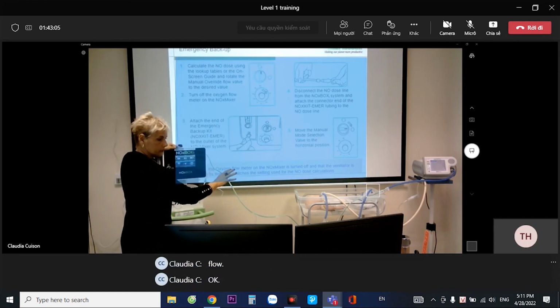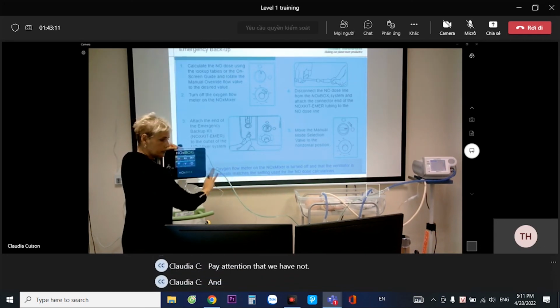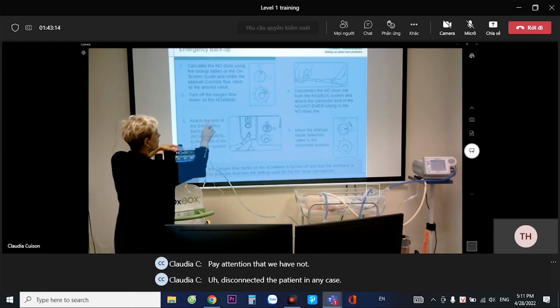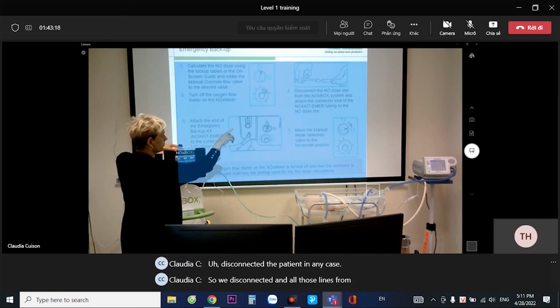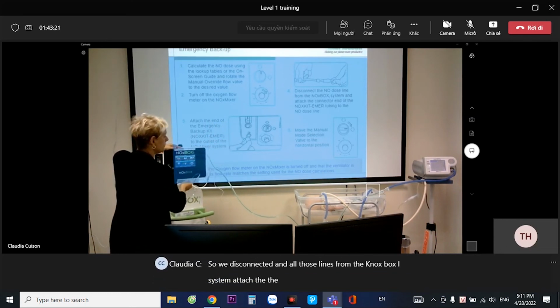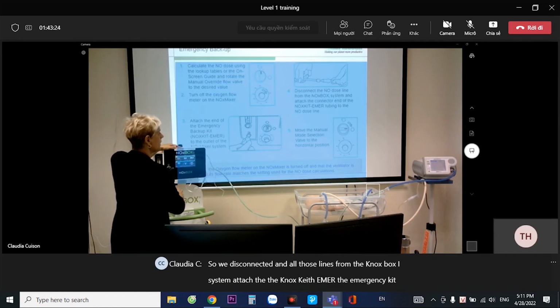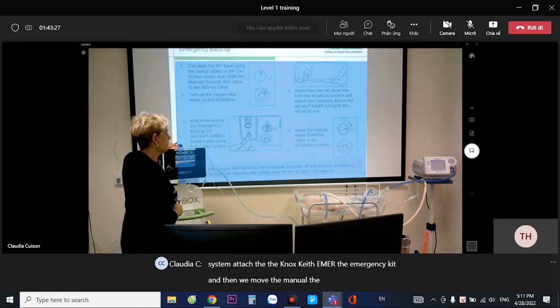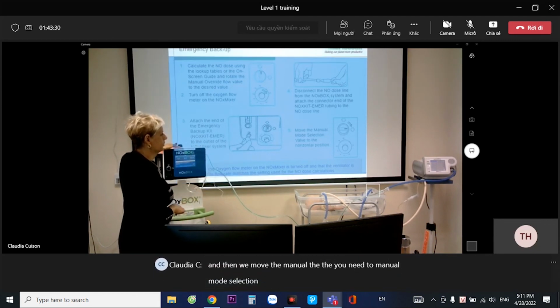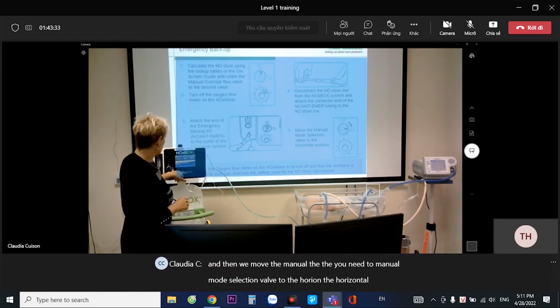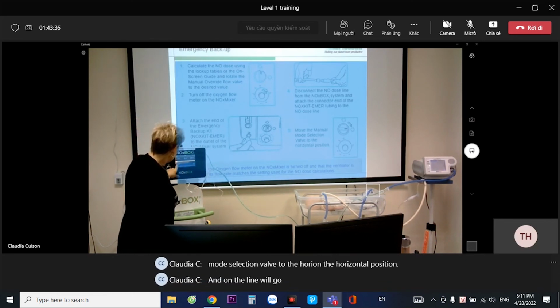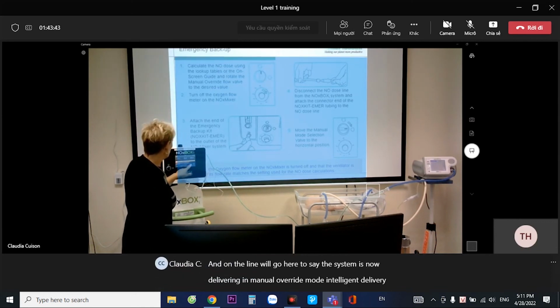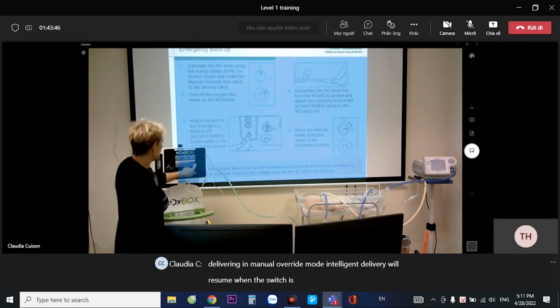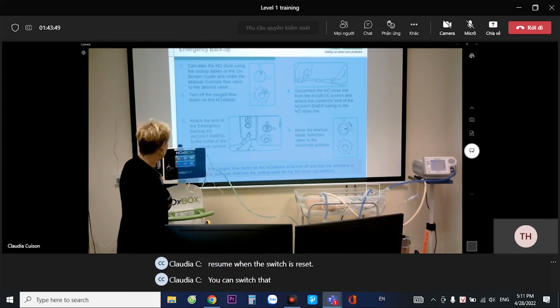Okay? Pay attention that we have not disconnected the patient in any case. So we disconnect the NO dose line from the NOxBOX i system, attach the NOx kit EMER, the emergency kit, and then move the unit's manual mode selection valve to the horizontal position. And an alarm will go here to say the system is now delivering in manual override mode. Intelligent delivery will resume when the switch is reset. You can switch that.